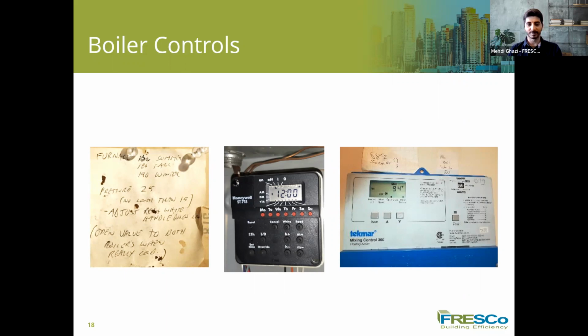Boiler controls, as I mentioned, for condensing boilers, it could be a condensing boiler or any type of existing boiler, a regular boiler. Sometimes, as you can see in the left photo, we just have some notes. This is quite common when we walk into boiler rooms in different buildings. We can see notes like this in the boiler rooms, and this is a sign that there might be no control, or the controls are being overridden manually. And these notes are a kind of instruction manual for the contractors or on-site maintenance team members to see how they can manually manage and control the system, instead of having a good control system working.